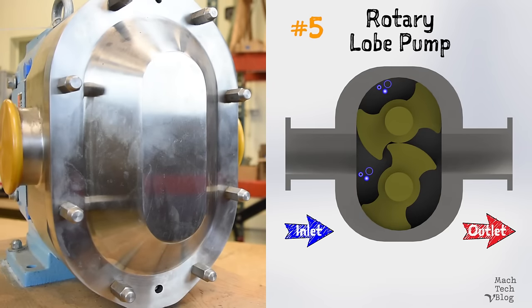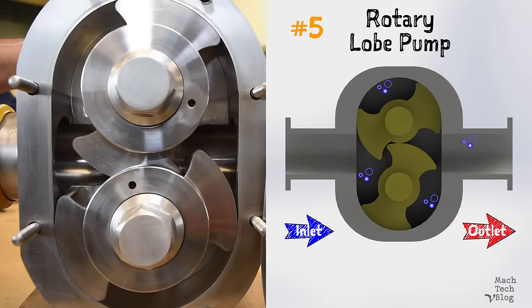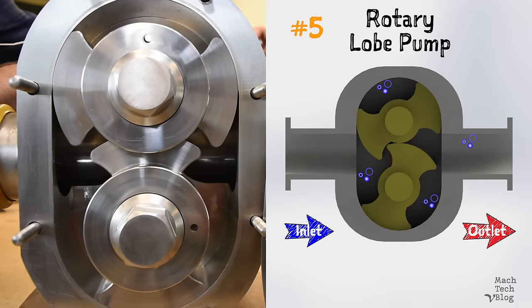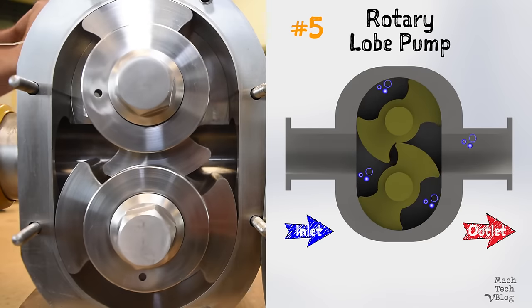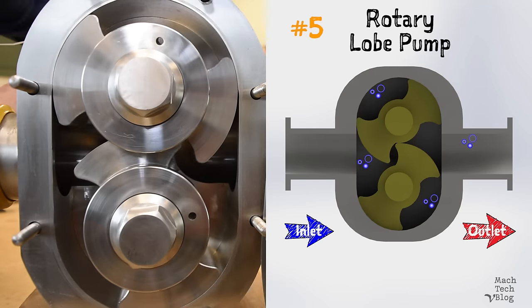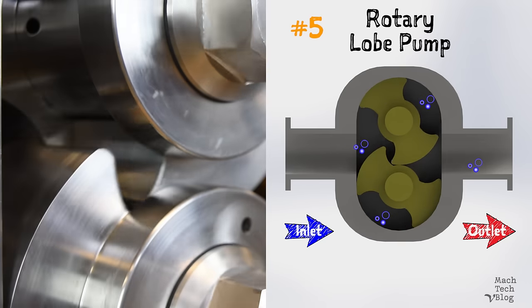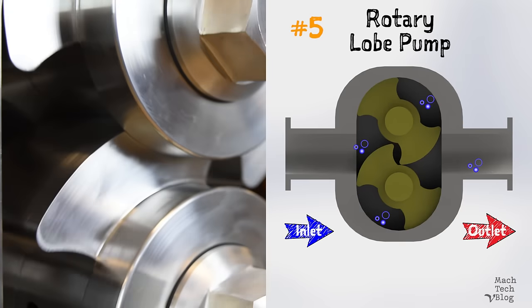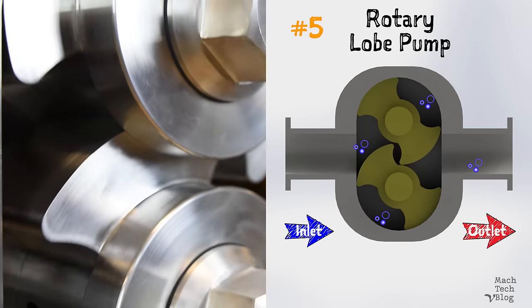Pump number five is the lobe pump. Lobe pumps function very similarly to external gear pumps, but the rotors are driven independently by external timing gears. The rotors have two or more lobes, and the moving chamber is formed between the outer surfaces of the lobes and the inside wall of the oval housing. As one of the lobes rotates back toward the center of the housing, the tight clearance between the lobe and the other rotor closes the chamber and forces the fluid through the discharge outlet.